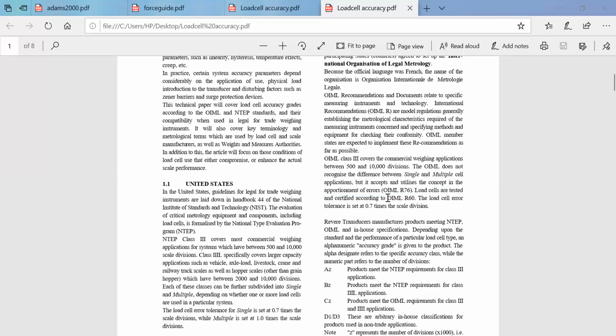As per the OIML R60 standard, whether it is a single or multiple cell, there is no need to classify the error differently, because they are calibrating and checking initially, and they will come to know whether there is error or not, and if so, how much must be deducted from the obtained result. This gives a clear picture of the error bar the load cell stands in, and its accuracy level.